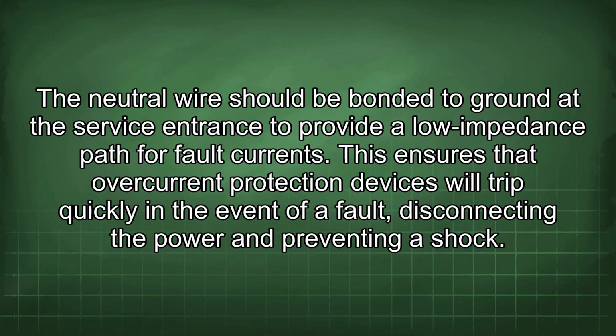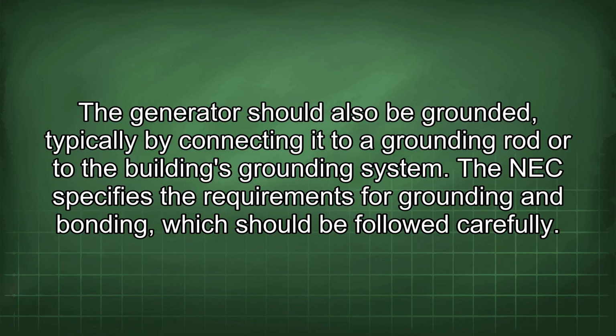The neutral wire should be bonded to ground at the service entrance to provide a low impedance path for fault currents. This ensures that overcurrent protection devices will trip quickly in the event of a fault, disconnecting the power and preventing a shock. The generator should also be grounded, typically by connecting it to a grounding rod or to the building's grounding system. The NEC specifies the requirements for grounding and bonding, which should be followed carefully.